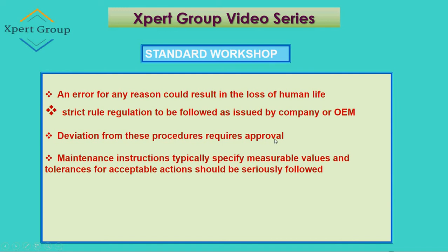Deviation from required procedures requires approval from the OEM, company, or manufacturer. Maintenance instructions typically specify measurable values and tolerances for acceptable actions, which should be seriously followed. The tool or instrument you are using needs to have a maintenance instruction that specifies the required values and limits.